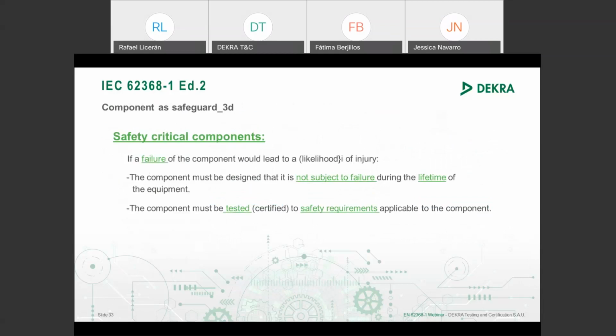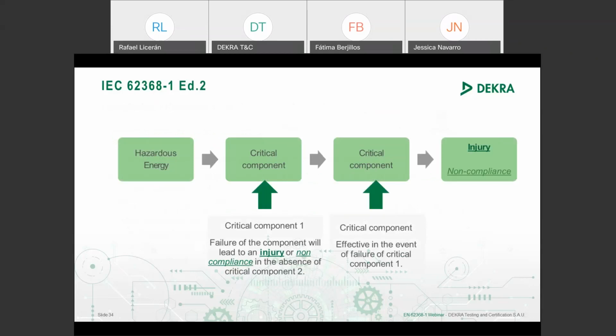Regarding safety critical components, when you use a component as a safeguard or a component bridging a safeguard, basic or reinforced, the component must always be certified to its component standard. If I have a capacitor between line and earth, I require that this capacitor meets the capacitor standard, the 60384 standard. And we have to check this capacitor with Annex G of this standard.